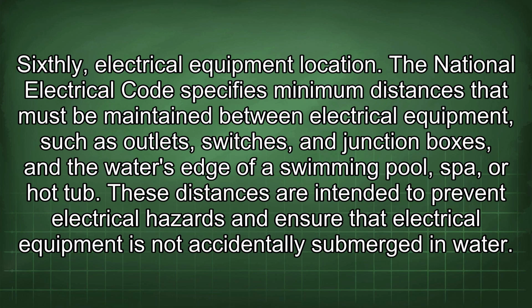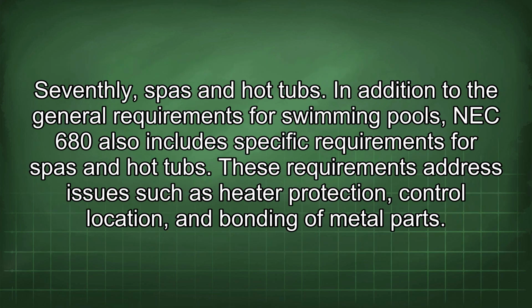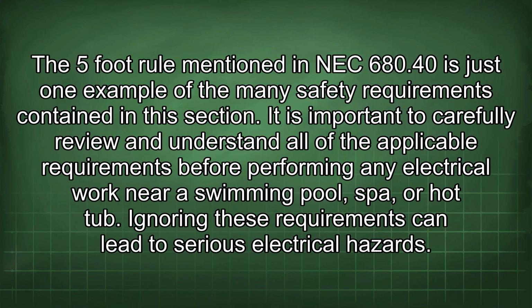These distances are intended to prevent electrical hazards and ensure that electrical equipment is not accidentally submerged in water. Seventhly, spas and hot tubs. In addition to the general requirements for swimming pools, NEC 680 also includes specific requirements for spas and hot tubs. These requirements address issues such as heater protection, control location, and bonding of metal parts. The 5-foot rule mentioned in NEC 680.40 is just one example of the many safety requirements contained in this section.